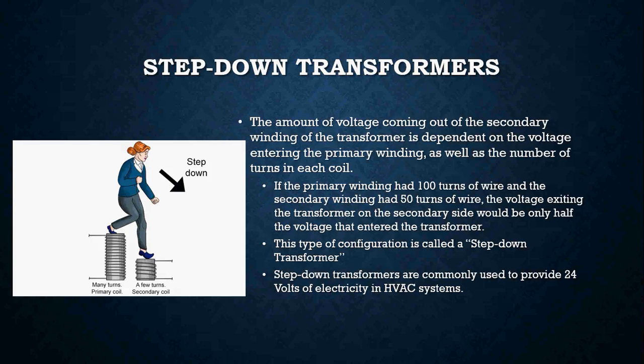The amount of voltage coming out of the secondary winding of a transformer is dependent on the voltage entering the primary winding as well as the number of turns on each coil. So if a primary winding has 100 turns of wire and the secondary winding only has 50, the voltage exiting that transformer on the secondary side would be only half the voltage that entered. That type of configuration is called a step-down transformer — it takes electricity from the primary side and steps it down to another voltage.